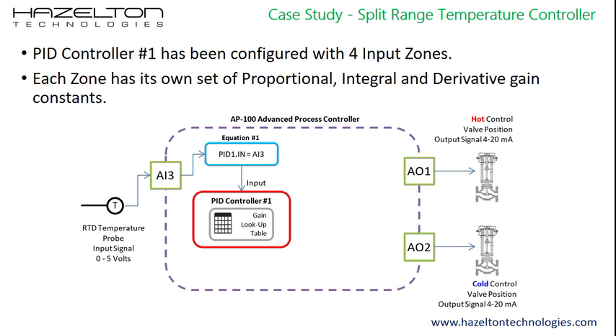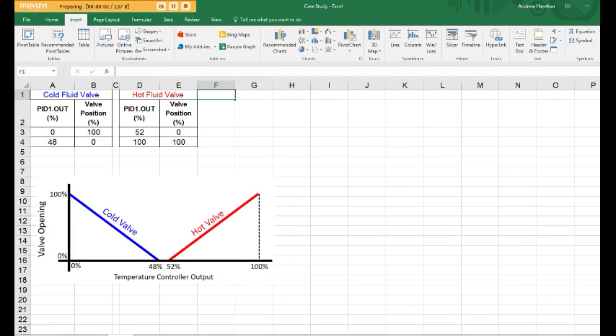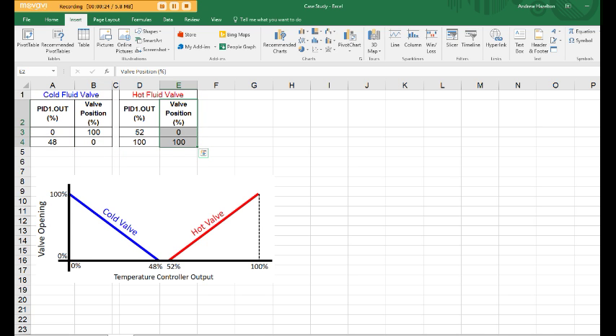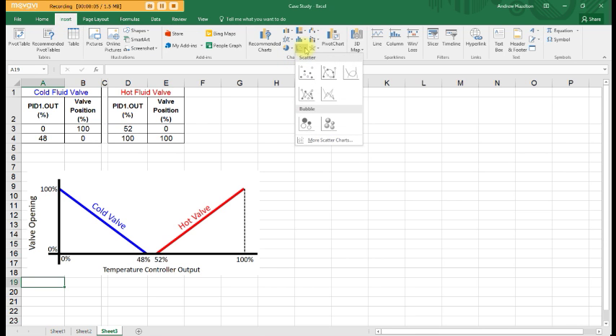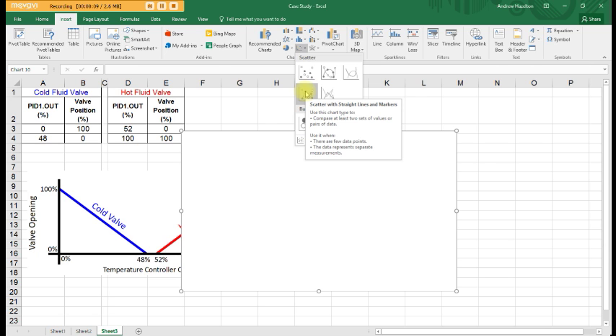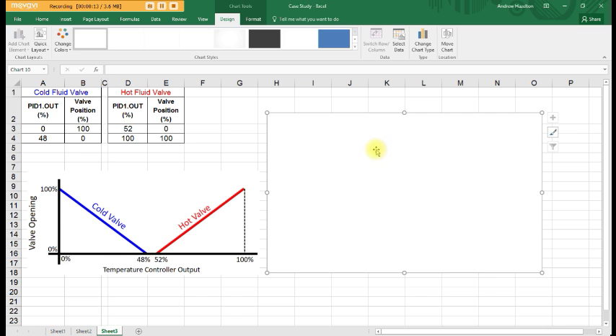To connect the PID output to the control valves, equations must be derived to ramp open and close each valve individually, executed using if statements. A graph is used to visualize this: the x-axis shows the PID controller output from 0 to 100%, and the y-axis shows the position of the hot and cold control valves. Two tables show controller output versus valve position. To create the chart, select the insert tab, go to the chart field, and select a drop-down X-Y scatter graph, then add the data points for the cold valve and the hot valve.